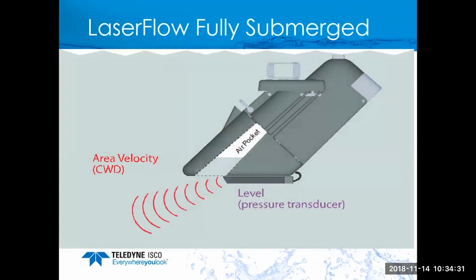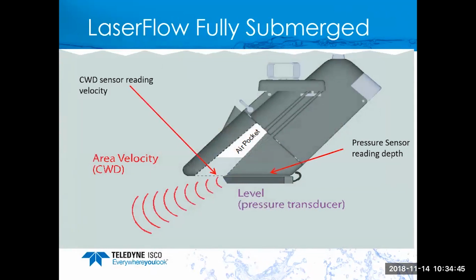So what does the laser do when it goes underwater? Well, it has a built-in continuous wave Doppler sensor that is on the bottom of the laser, mounted upside down. It uses continuous wave Doppler to measure the velocity and a pressure transducer to measure the level. So now you're going to get very accurate level measurement, and very accurate velocity when that pipe goes full. And the reason is because peak velocity, or the highest velocity, is typically towards the top.